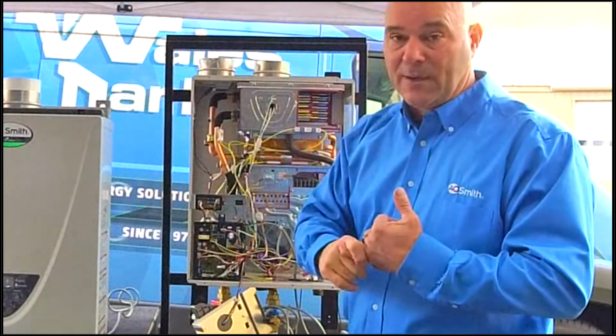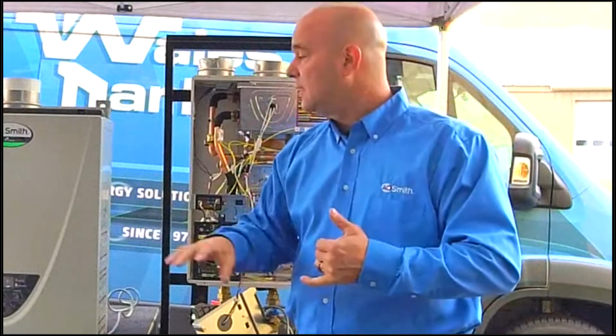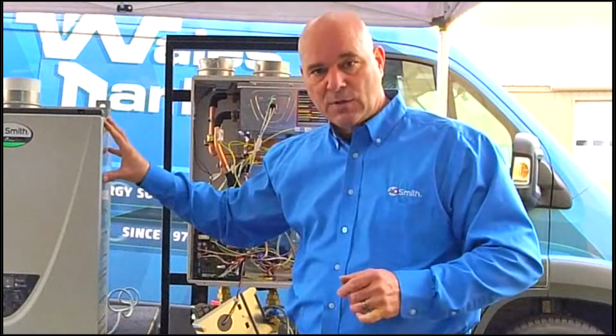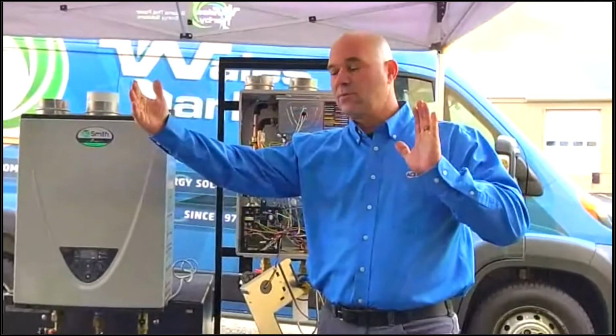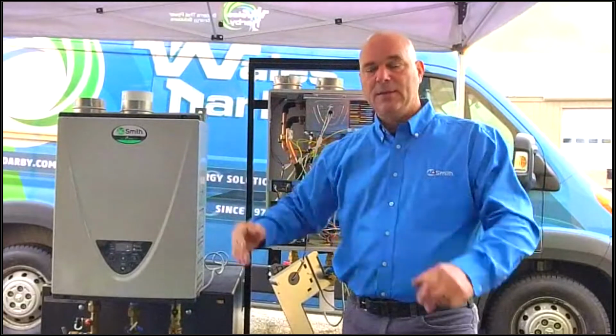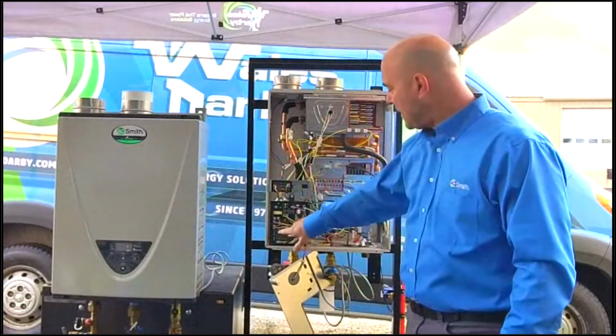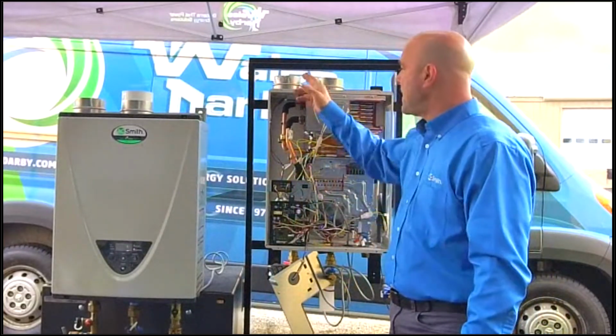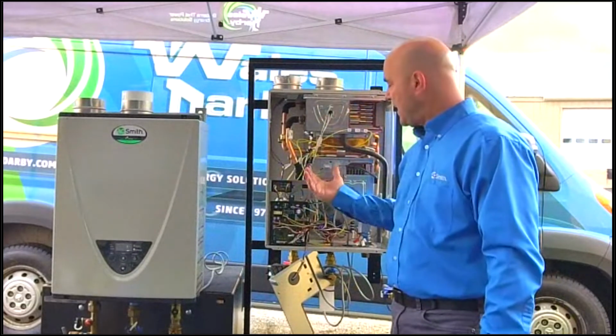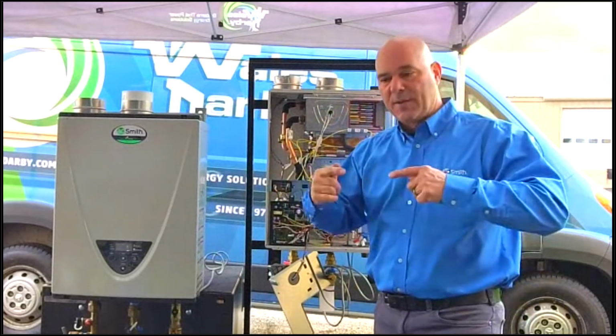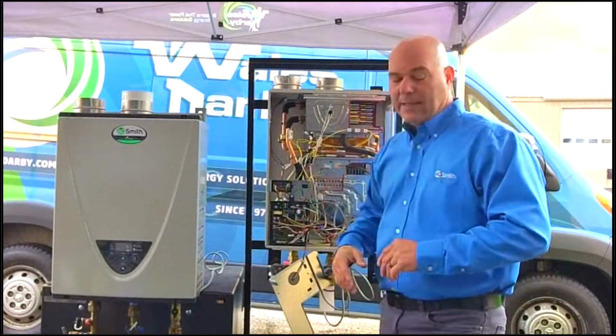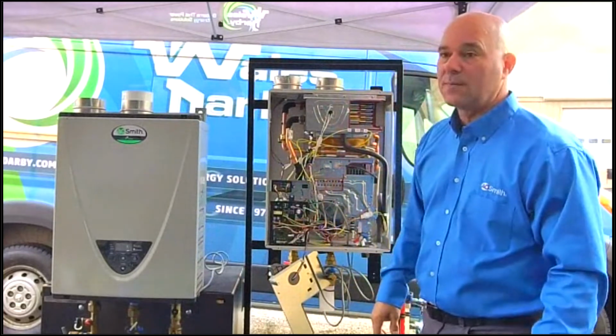Elbows, long sweep elbows. That's what you want to use when you're venting heating equipment, hot water heating equipment. We're going to use long sweep elbows. It's a smoother bend, doesn't create as much equivalent feet of pipe. So make your dip switch changes, let that marry up to your venting system. That will tell the unit to change its RPM of the blower when it's running, and that will make the system run properly.